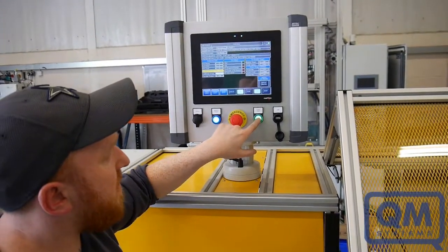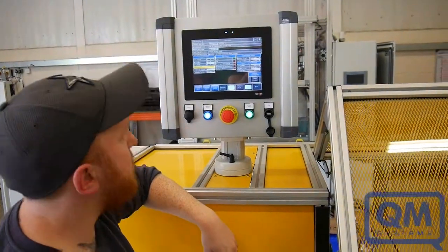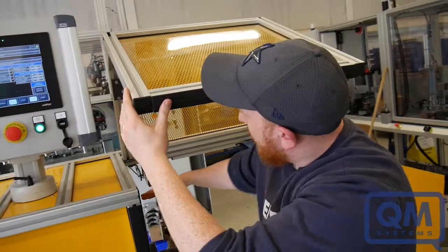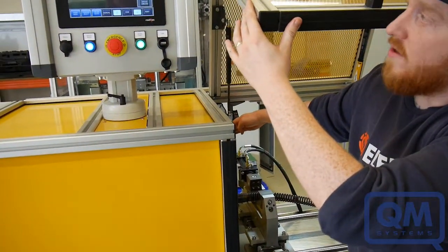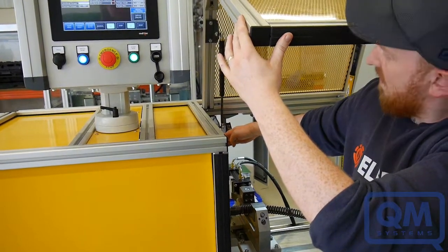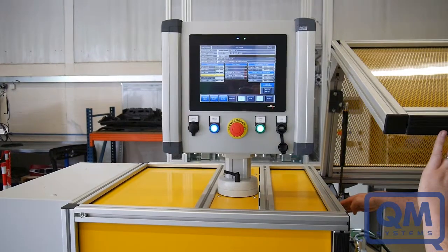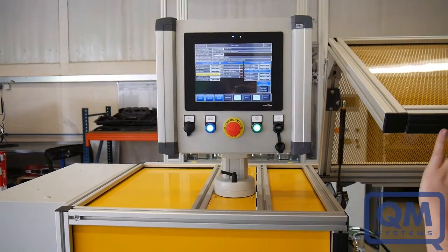If I hold the test start for a small delay, it's now saying it's waiting for the guard door to be locked. There is an interlock in place on this step, where if I tell the part in place that it's no longer there, the screen should say that it's waiting for an interlock of the part present. If I show the screen edge, the message reads action 4 lock, waiting for guard door for part present. If I tell it the part is there, it reverts back to waiting for guard door locked. We can close the guard door.